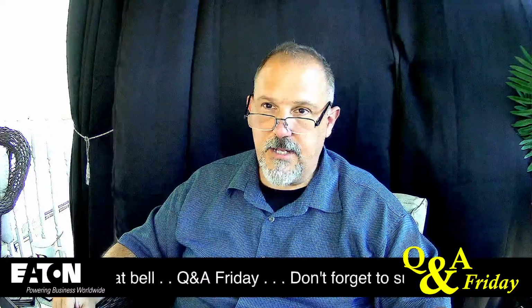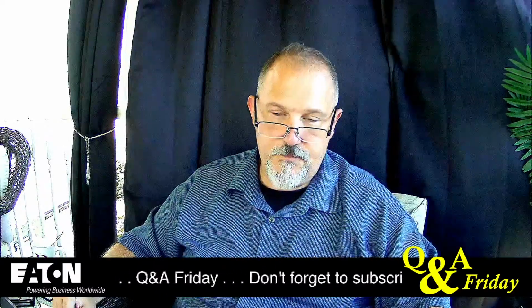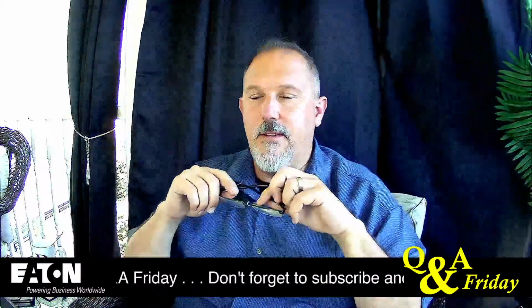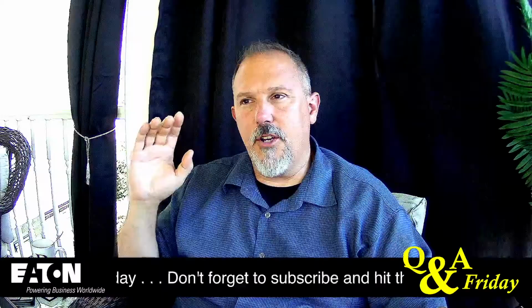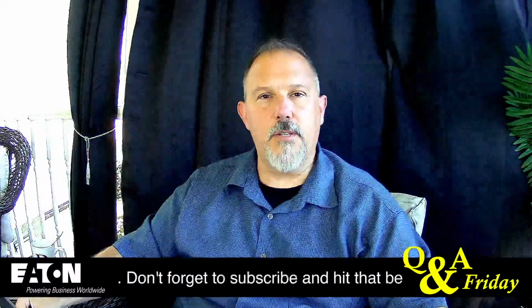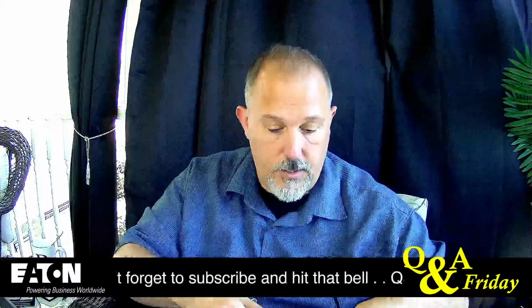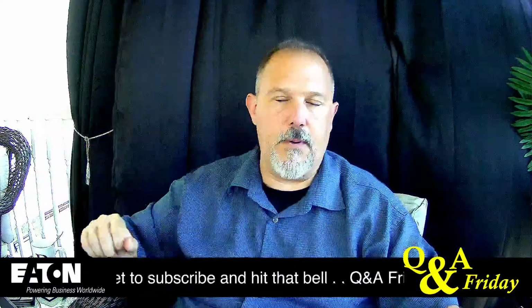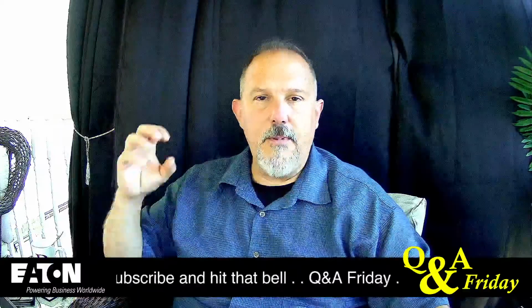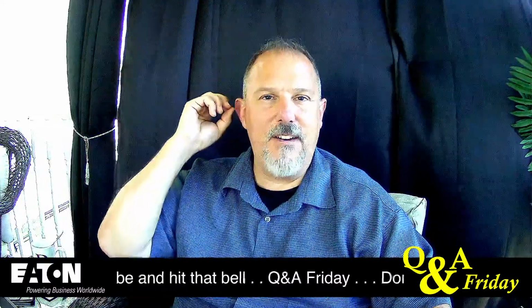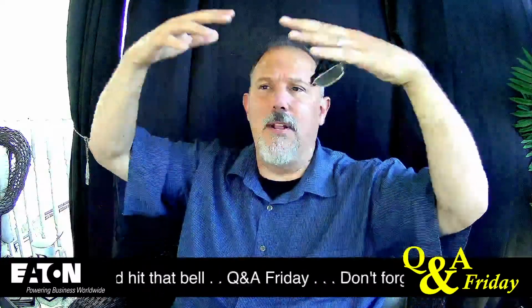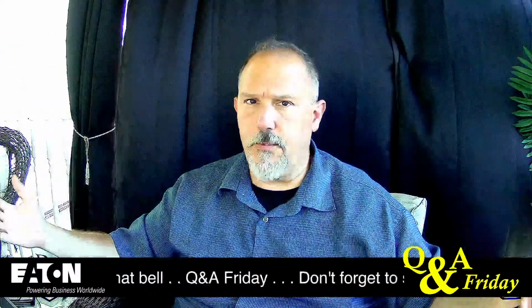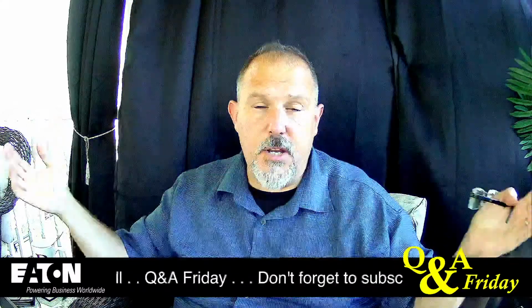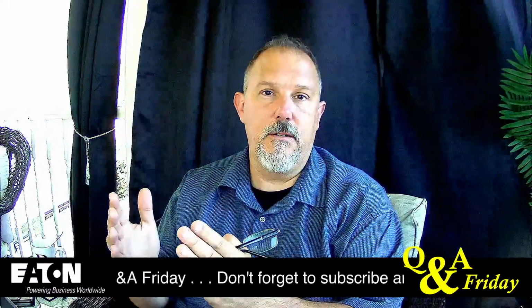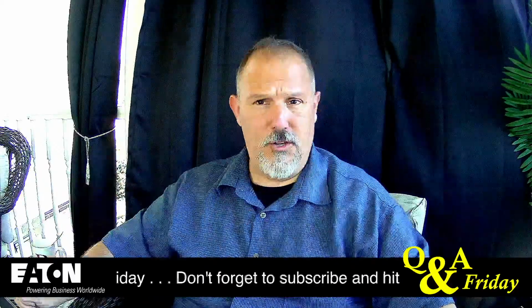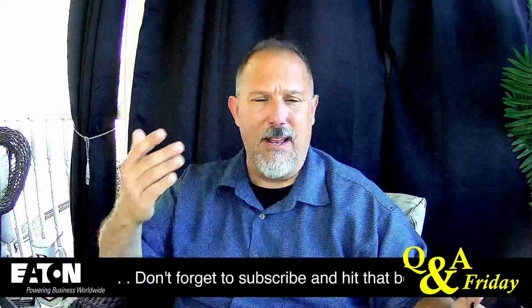I would love to do some tests, because here's my thought process. If my current is in the instantaneous region of my main overcurrent protective device, line side propagation, to your point, you're saying that the IEEE standard says you could have line side propagation. If I'm in the current limiting region of my overcurrent protective device and I have nothing but a spark, there's no plasma cloud, there's no major disruption of current. It's up and it's gone because I opened so fast. You don't have the plasma to do a line side propagation.